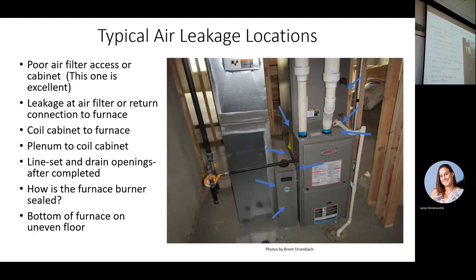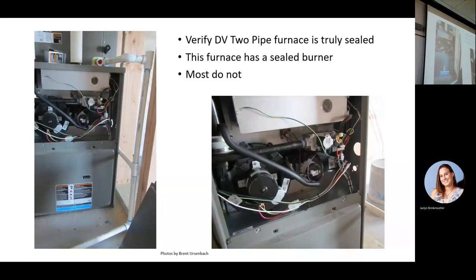So here are the places that they really leak. Number one, the holes in your coil cabinets where your drains and everything come through, where you hook it down onto the furnace all the way around, where your filter cabinet hooks onto the side of the furnace, where the drop hooks on the side of the filter cabinet, and the bottom of the furnace. In years past, I think most of them were sealed better in the bottom. But these are your big sources of a lot of leakage, and they can be taken care of simply with a little bit of effort, and it looks a lot better than smearing the crap all over your coil cabinet and your furnace. The drain hole and your line set holes really leak a lot, and those need to be sealed.